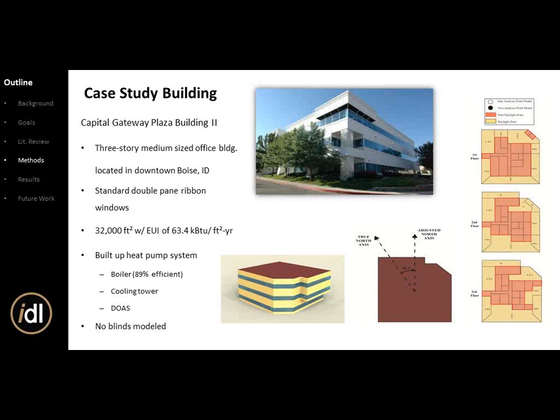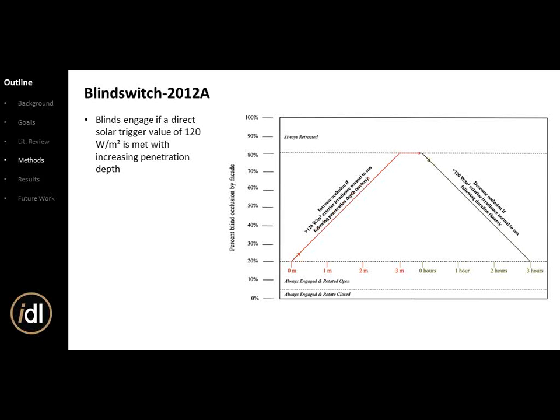Here's the floor-by-floor layout. The yellow zones are the daylight zones with daylight sensors, and the red zones are the core zones. One takeaway is that this is a core-zone-dominated building, so daylight shouldn't be the main component. I placed three sensors per zone — one nearest the window, one in the middle, one in the back — to give a better idea of daylight penetration. EnergyPlus only allows two sensors per zone, so I actually had to do two different models.